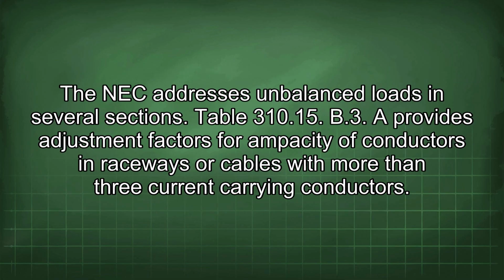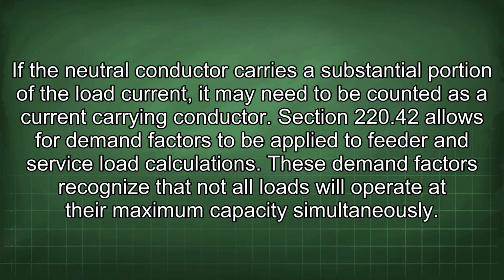The NEC addresses unbalanced loads in several sections. Table 310.15(B)(3) provides adjustment factors for ampacity of conductors in raceways or cables with more than 3 current-carrying conductors. If the neutral conductor carries a substantial portion of the load current, it may need to be counted as a current-carrying conductor.